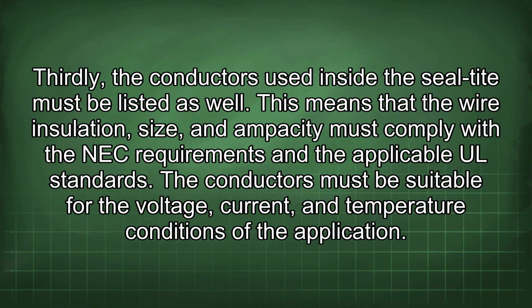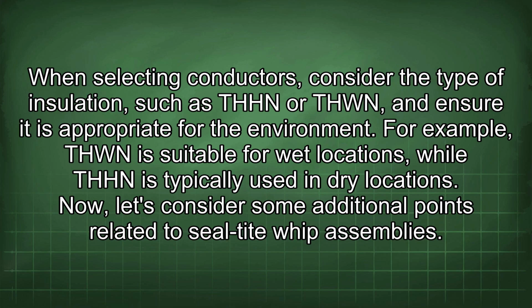Thirdly, the conductors used inside this Seal-Tite must be listed as well. This means that the wire insulation, size, and ampacity must comply with the NEC requirements and the applicable UL standards. The conductors must be suitable for the voltage, current, and temperature conditions of the application. When selecting conductors, consider the type of insulation, such as THHN or THWN, and ensure it is appropriate for the environment. For example, THWN is suitable for wet locations, while THHN is typically used in dry locations.